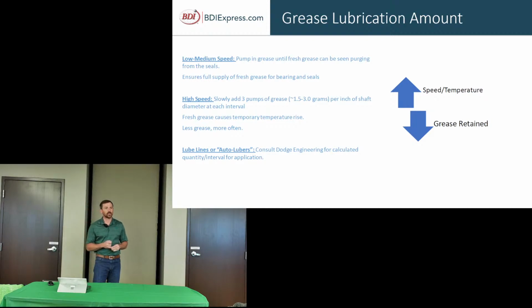Does anybody use the automatic lubricators where it just pumps in grease? There's some that are spring operated, battery operated, or gas operated. What these do is, people think you're trying to replace some tech's job of going around to a bunch of air handling units to grease them, but it alleviates that need and ensures you're getting the right amount of grease. There's dials that you set on them based on the application and bearing size, that'll automatically put that in to make sure you're not over greasing or under greasing. It's making sure that you're getting the right amount in there.